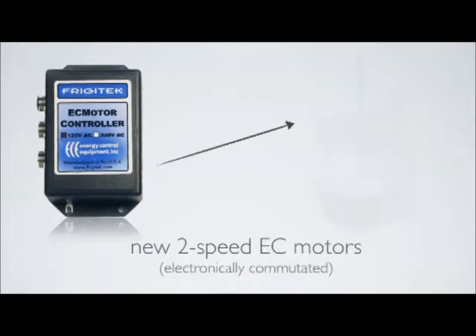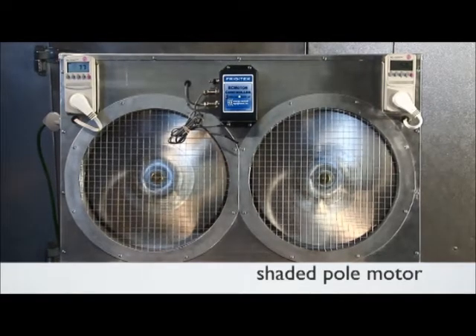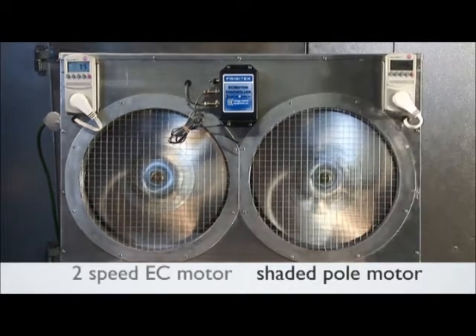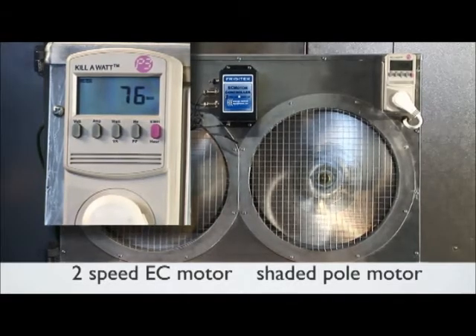Frigitek works in conjunction with the new 2-speed EC motors that are far more efficient than the shaded pole motors currently found in most walk-ins. Here's a demo unit that will clearly show the effectiveness of Frigitek. To the right is a fan being driven by a standard shaded pole motor — it's consuming about 149 watts. On the left is a new 2-speed EC motor, consuming about half the energy, or about 76 watts.